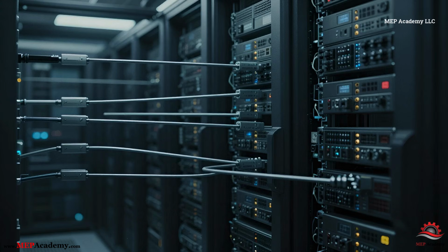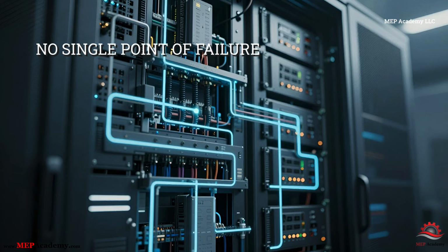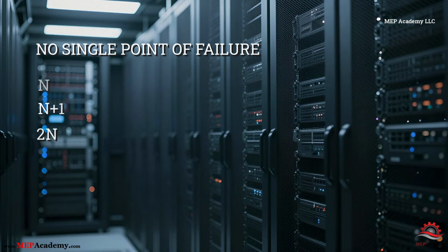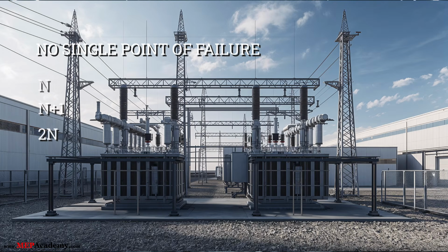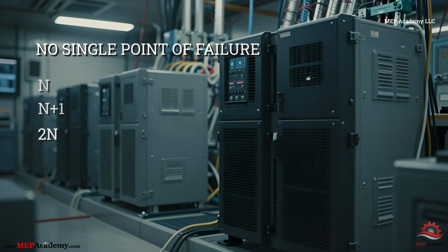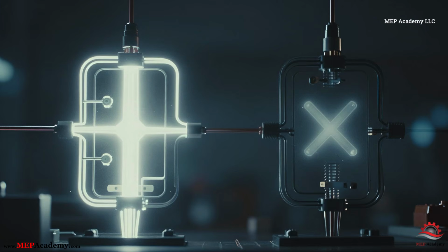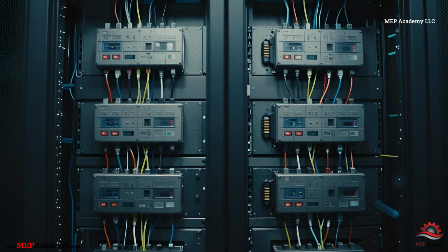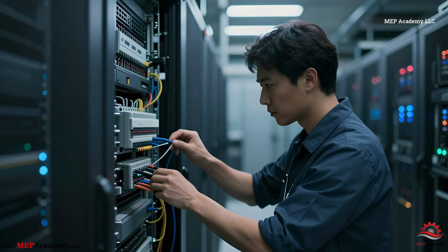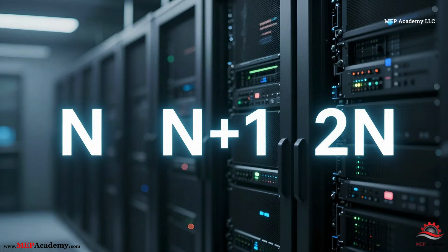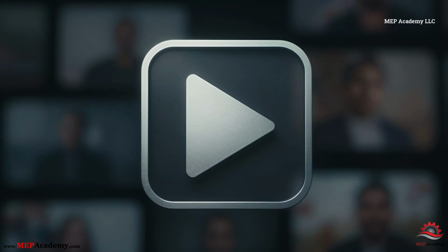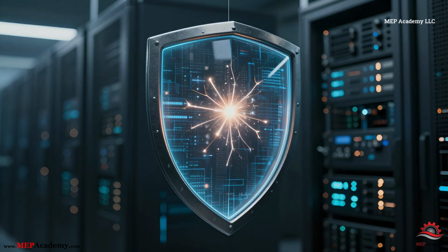Now let's look at the third key concept: redundancy. Redundancy is one of the most important design principles in data center electrical systems. Instead of relying on a single piece of equipment, data centers often install duplicate systems. For example, a facility might have 2 independent electrical feeds from the utility grid. It may also include multiple UPS systems, multiple generators, and multiple electrical distribution paths. This means that if one piece of equipment fails, another system is already available to carry the load. Some high-reliability facilities even design the electrical system so that entire power paths are duplicated, allowing maintenance or failures to occur without interrupting operations. You may hear these redundancy strategies described using terms like N, N+1, or 2N, which we discussed in our earlier video on redundancy design. The goal is simple. No single failure should ever take down the data center.